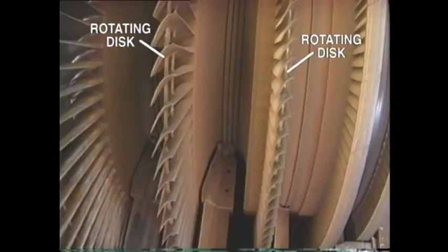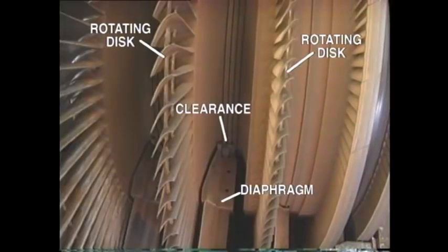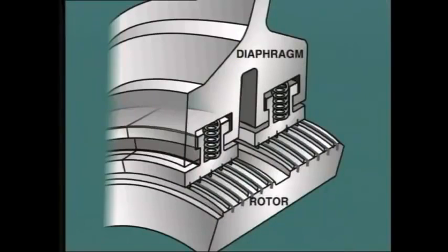And here is a view of the bottom half of a turbine casing with the diaphragms in place. The diaphragms are sized to leave a small inside clearance to allow the shaft to rotate. Seal strips are fitted at this location to prevent steam leakage. After all, we want all steam to pass through the blading, not around it. And we'll be talking about steam seals later.